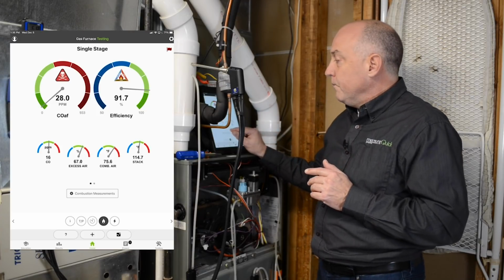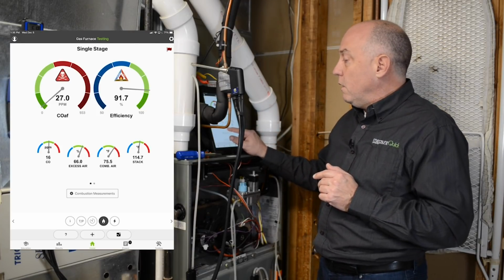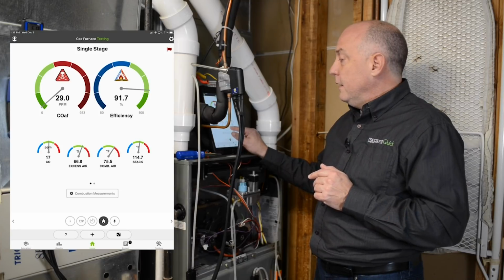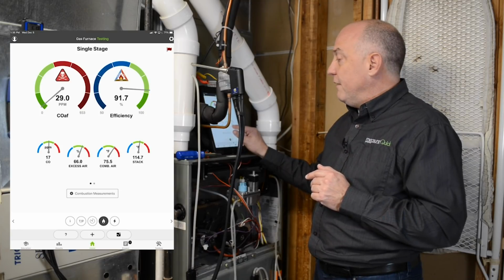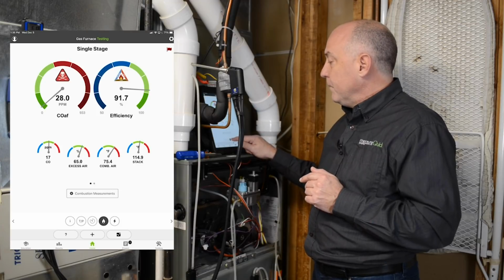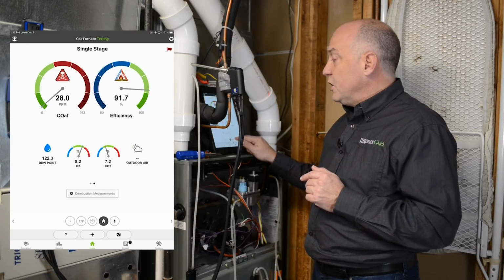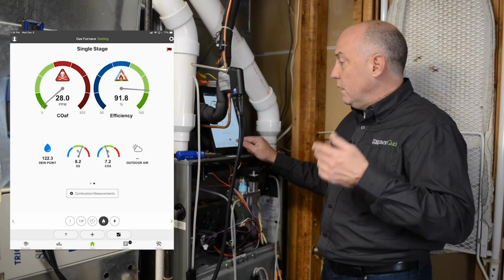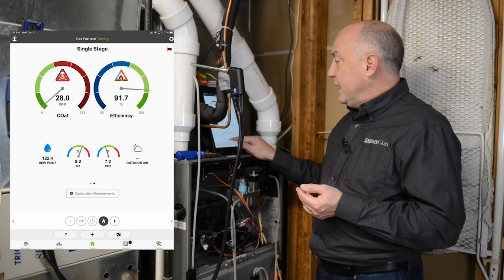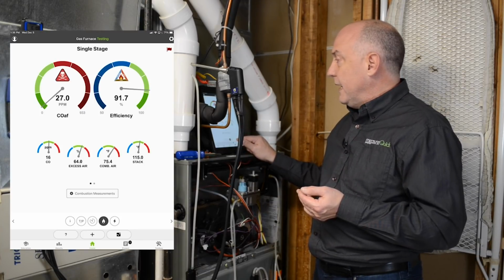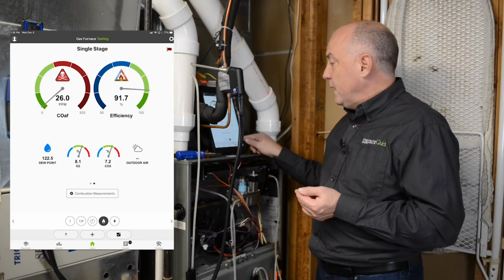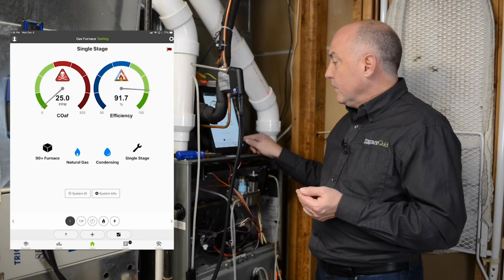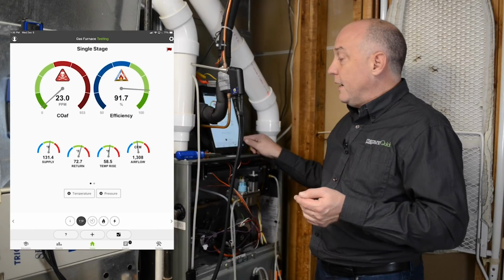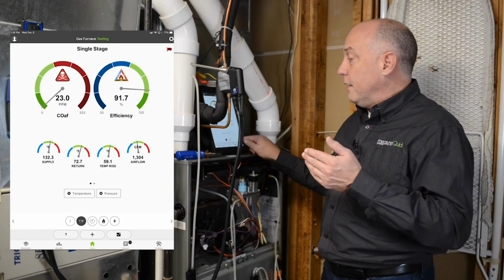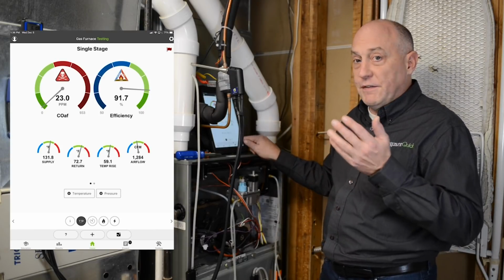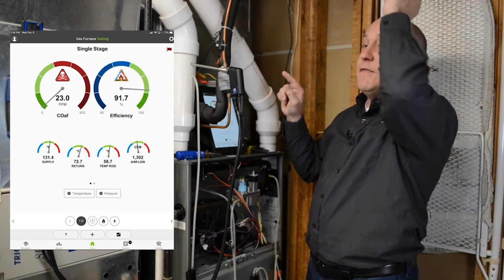So you can see right now we've got about 16 parts per million CO, 66% excess air, our combustion air temperature is 75 degrees, our stack temperature is 114. If I tap on the flame again, it's going to show us our dew point temperature, our O2, our CO2, and if I tap on it again, it's going to go back to stack temperatures and all that kind of stuff. And then we can scroll through here and look at all of our different readings. Natural gas furnace, supply air, 131.4, return air, 72 degrees, temperature rise, 59.6 degrees. I'm pulling those off the Testo probes.